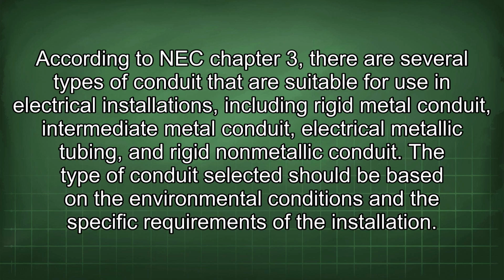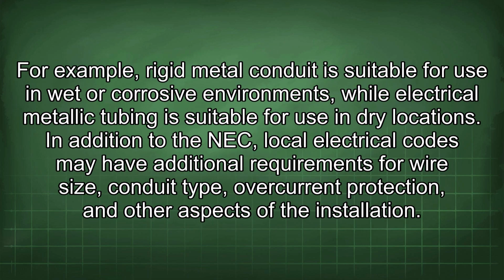According to NEC Chapter 3, there are several types of conduit that are suitable for use in electrical installations, including rigid metal conduit, intermediate metal conduit, electrical metallic tubing, and rigid non-metallic conduit. The type of conduit selected should be based on the environmental conditions and the specific requirements of the installation. For example, rigid metal conduit is suitable for use in wet or corrosive environments, while electrical metallic tubing is suitable for use in dry locations.